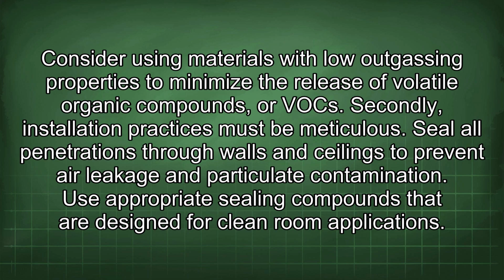Secondly, installation practices must be meticulous. Seal all penetrations through walls and ceilings to prevent air leakage and particulate contamination. Use appropriate sealing compounds that are designed for clean room applications.